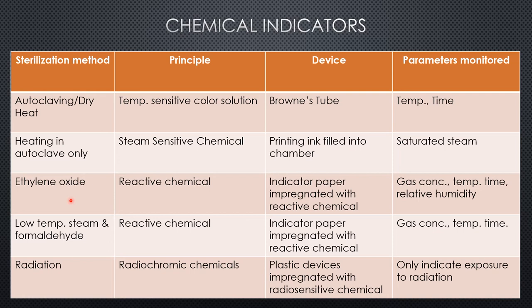For sterilization by low temperature steam and formaldehyde, a reactive chemical is again used. Similarly, an indicator paper impregnated with a temperature-sensitive reactive chemical undergoes a color change during the sterilization process. The parameters monitored are gas concentration, temperature, and time.